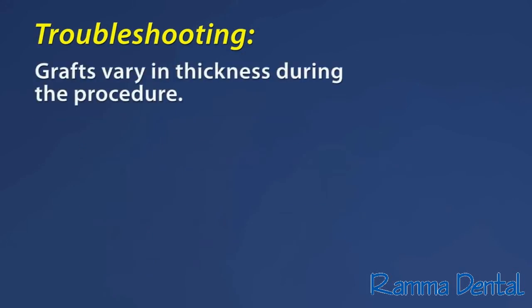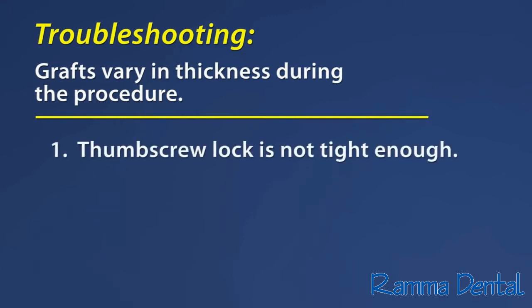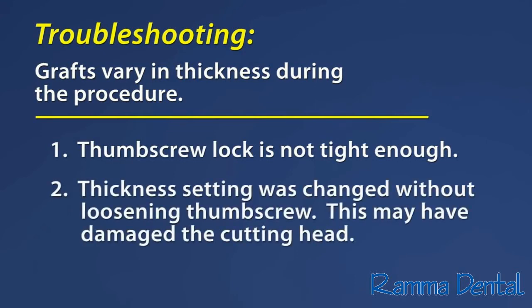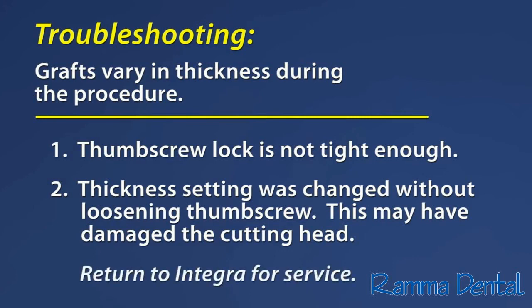A variation in graft thickness is observed during the procedure. 1. The thumb screw lock feature on the thickness knob is not sufficiently tightened to hold the knob at the user-selected thickness setting. 2. The thumb screw must be loosened prior to positioning the thickness knob pointer. Failure to loosen the thumb screw can result in physical damage to the dermatome's cutting head in the thickness knob area. This can significantly diminish the effectiveness of the thumb screw lock. If such visual damage is observed, the unit should be returned to the Integra Padgett Dermatome Repair Center for service.